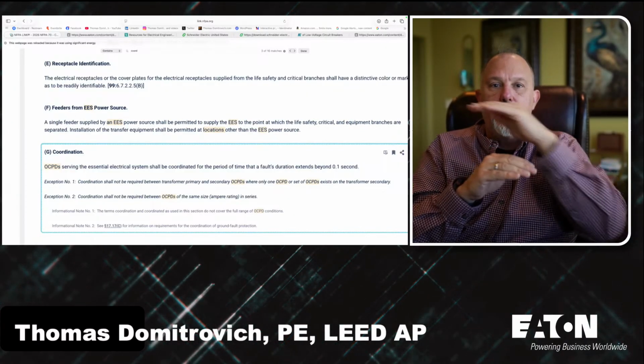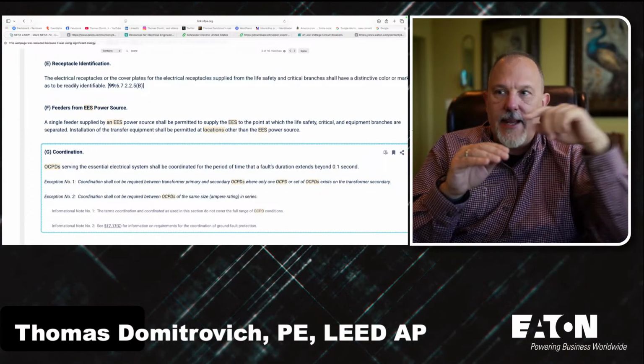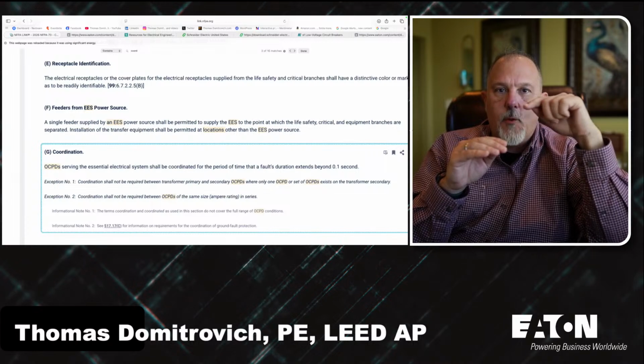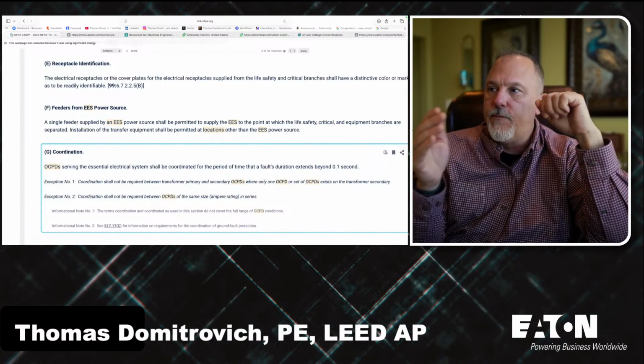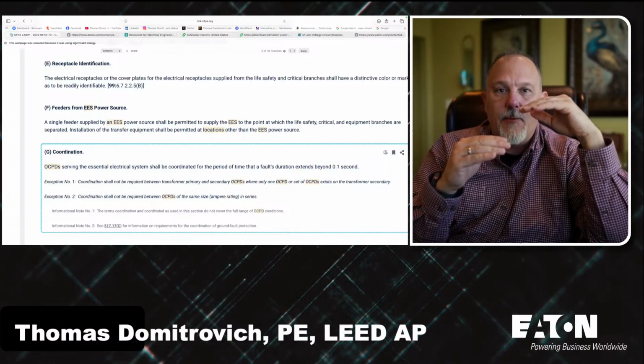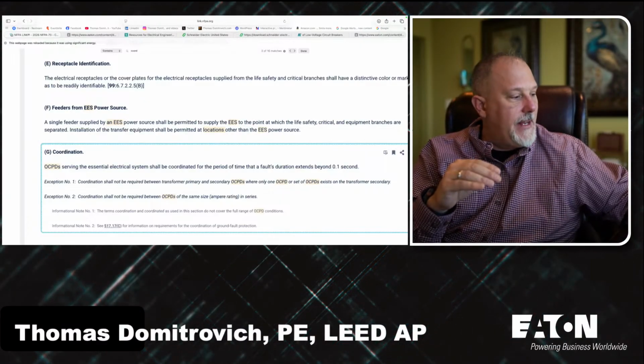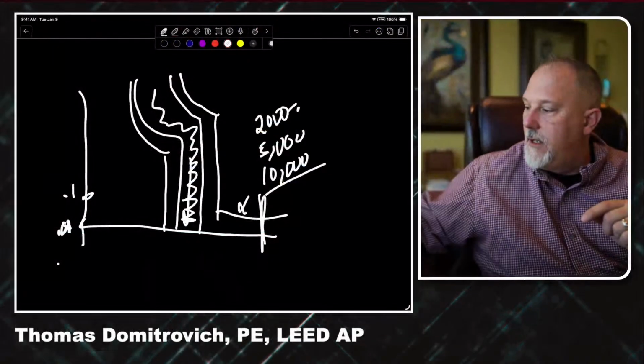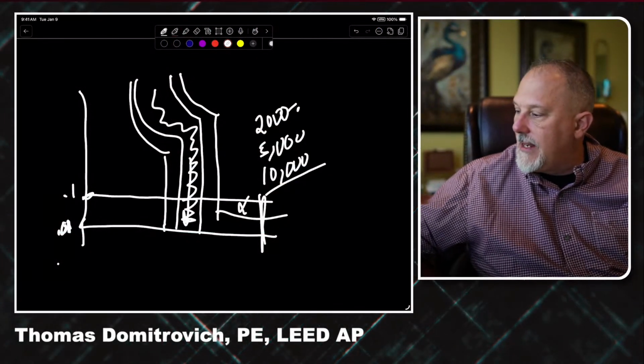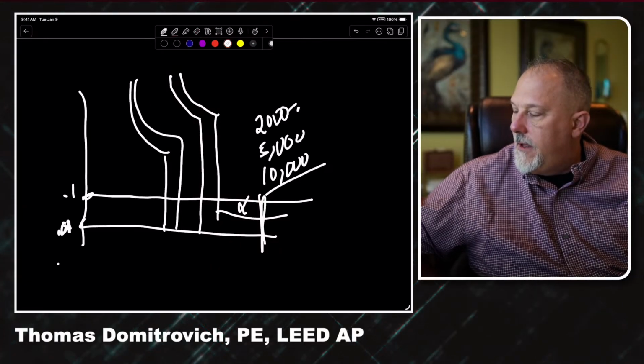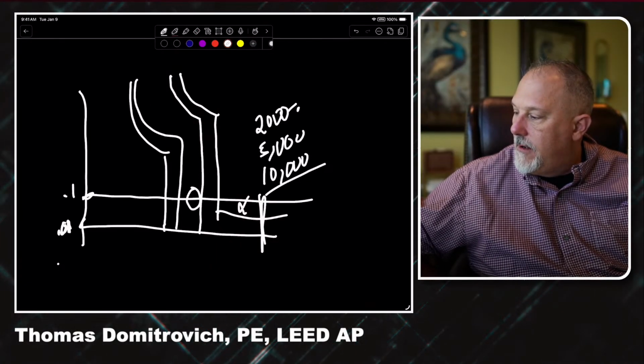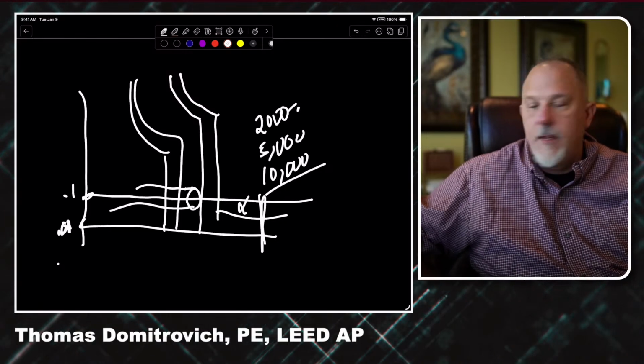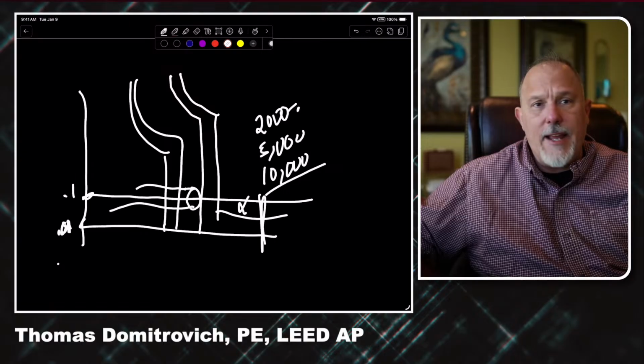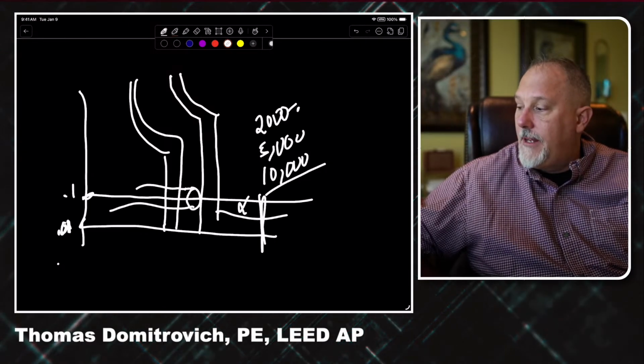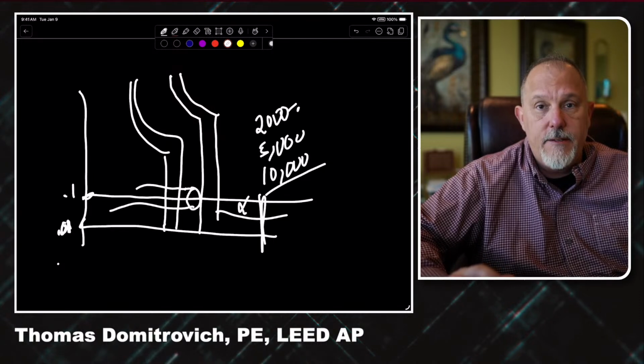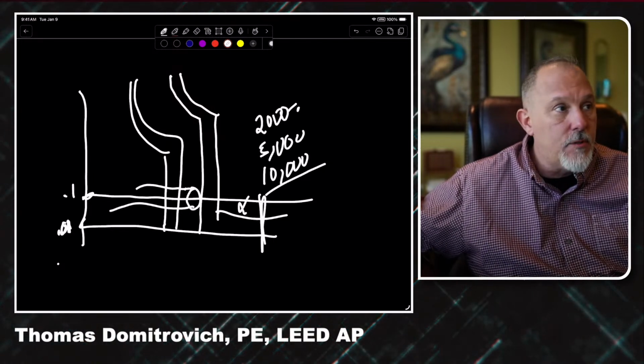So I would look at that 0.1 second line and say, I only have to worry about any current that would go beyond 0.1 seconds. So if I draw my 0.1 second line, that is everything over here and down, right? So it's only looking at those overloads. And if I selectively coordinate, I'm going to meet the coordination rules.